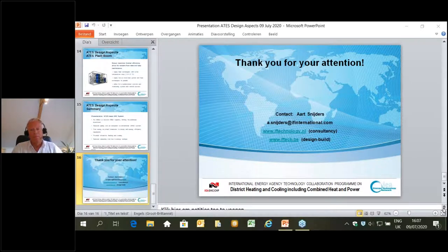Great. There was another question. It asks, how does ATES compare with BTES, in cost and efficiency? You'd like to have a stab at it, and then I can maybe complement your answer. Pat? Okay. In general, if you have a good aquifer, an ATES system is less expensive than a BTES system. Except for very small projects, then the BTES system is less expensive than the ATES system because you have a basic cost to install an ATES system.